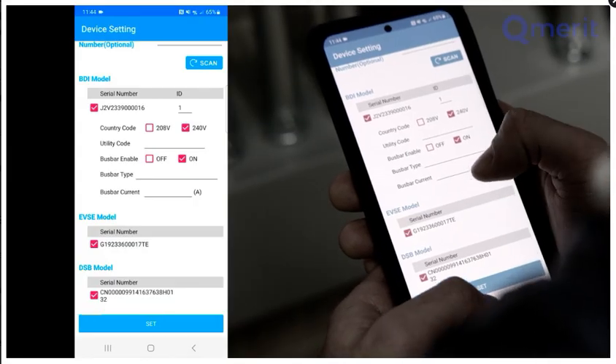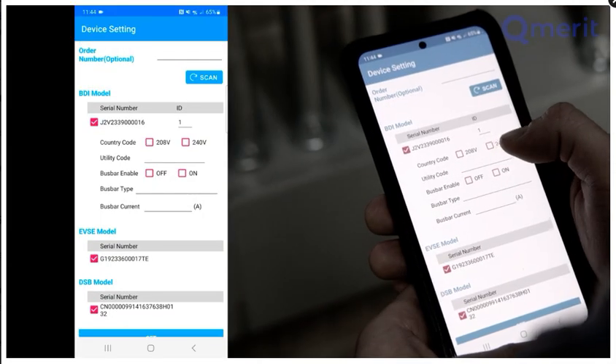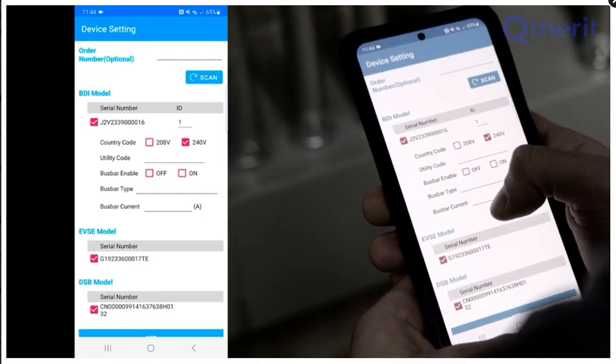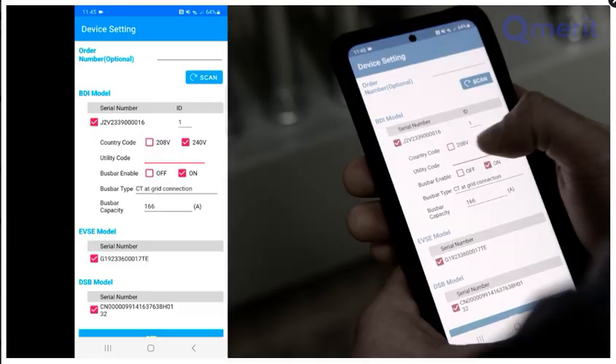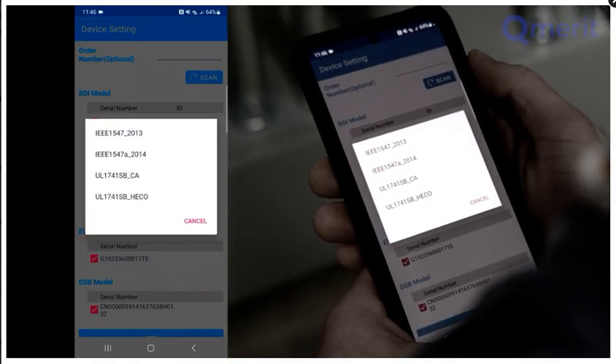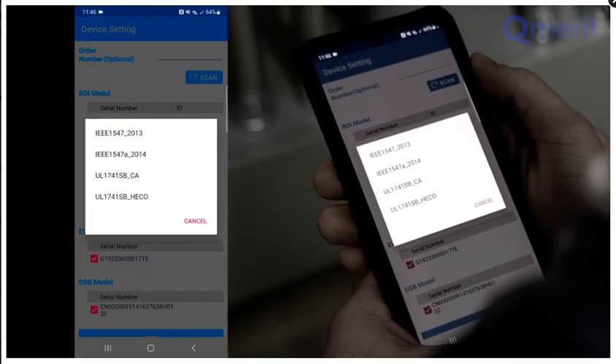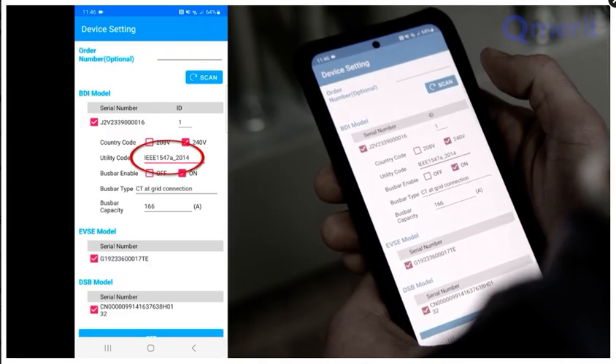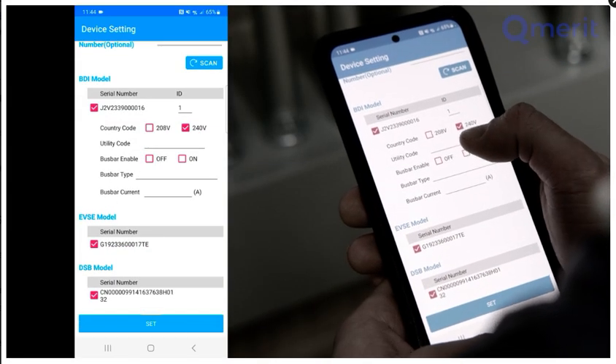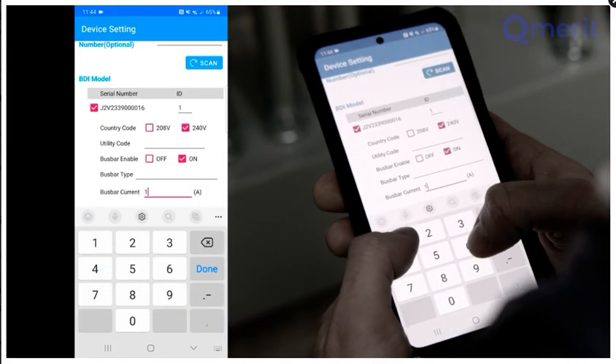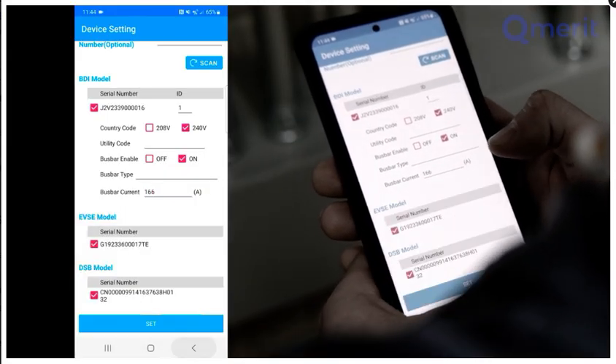The device setting screen will appear. Select 240 volts for the country code. Select the utility code. You will get 4 options to select a utility code. Select IEEE 1547A 2014. Busbar Enable, select On. Busbar current is 166 amps.